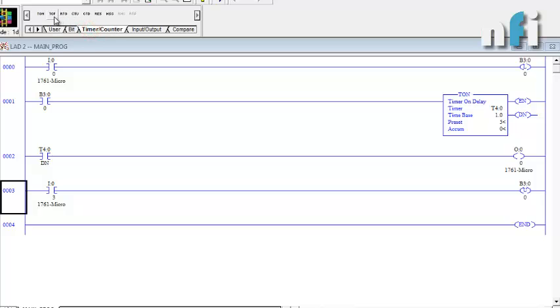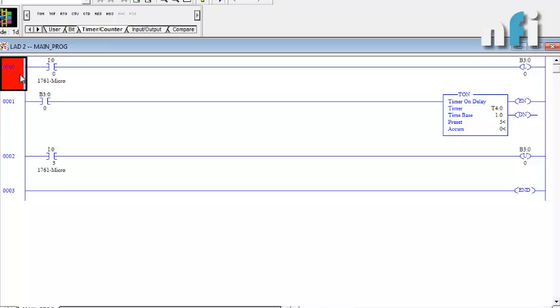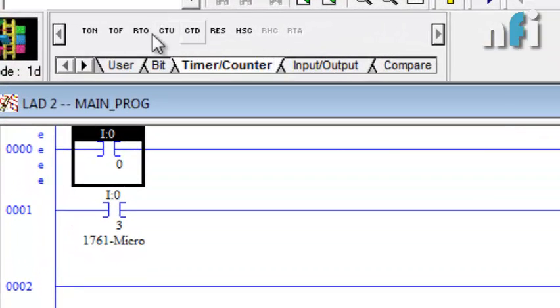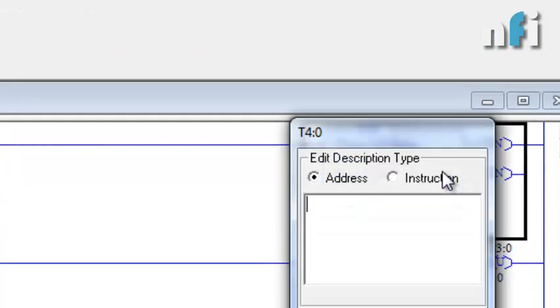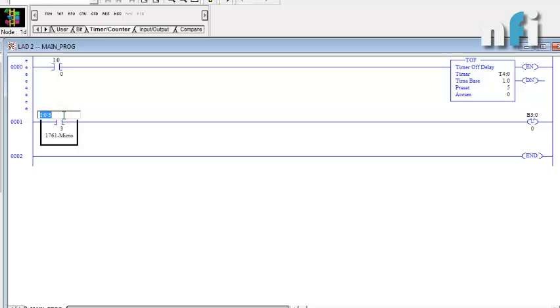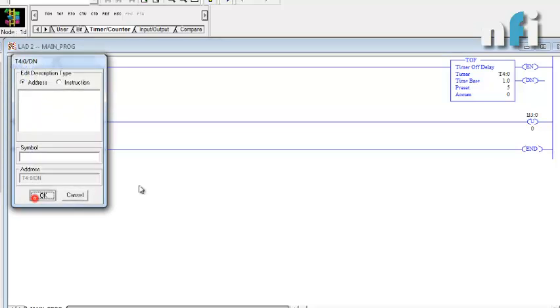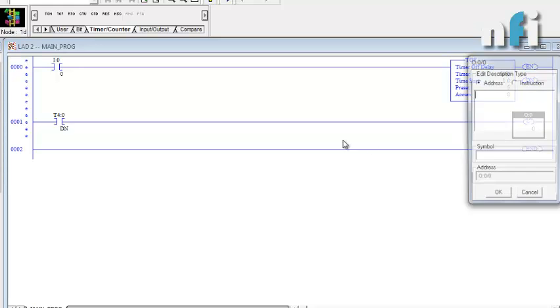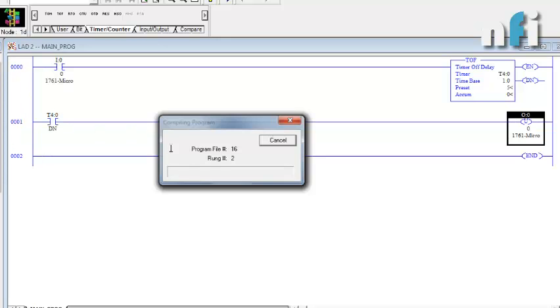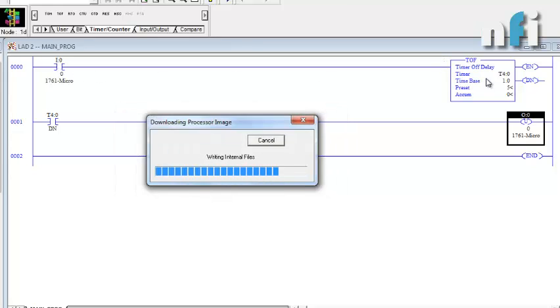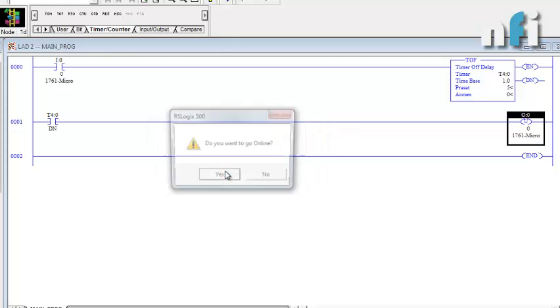That was about TON. Now we have another timer which is TOF — Timer Off Delay. There's a slight difference. Instead of TON, let's use TOF here. I'll take the same address T4:0, time base 1, preset 5, accumulator 0, and use T4:0/DN at the output. This timer says it is an off delay — if I turn on the timer by pressing IN0, the output will get off after five seconds.